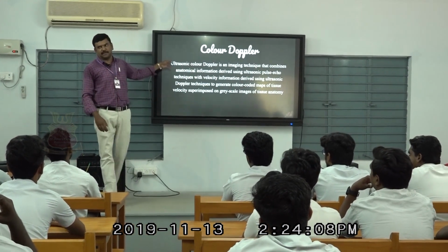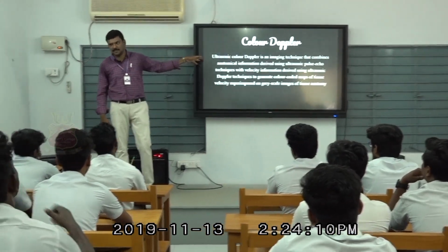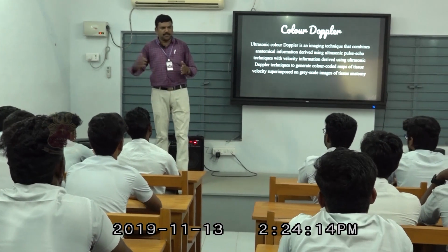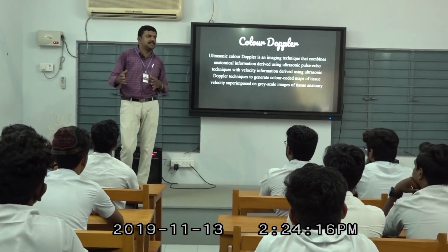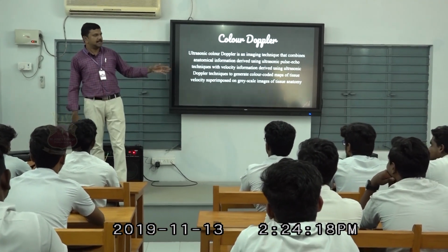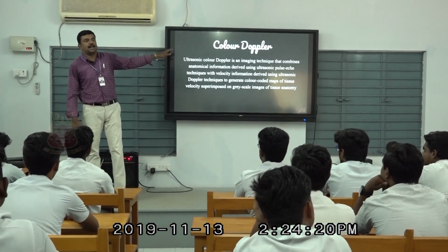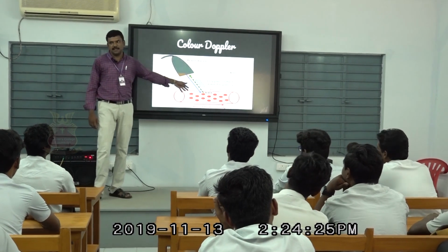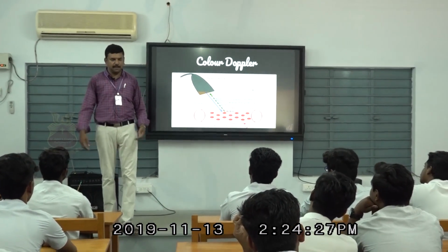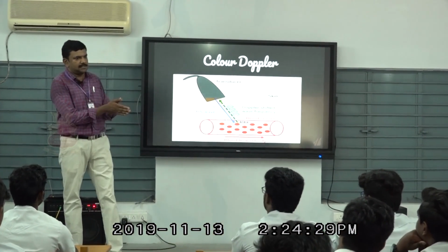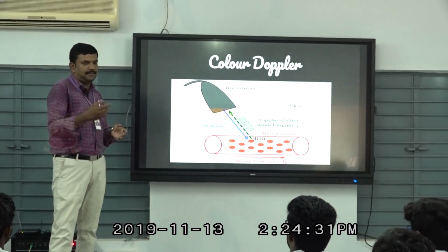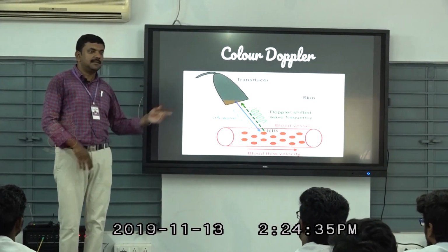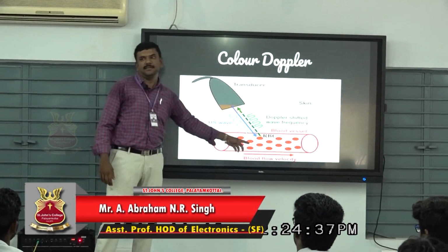That is due to the Doppler effect. Doppler is the name of a scientist. He studied the effect and it is called the Doppler effect. The approaching or departing will change the frequency of the audio. The similar way is used in this, and the ultrasound frequency is altered by the speed of the red blood cells of our body. When there is a blood flow, if you direct an ultrasound range sensor, the return wave will have some varying frequency depending upon the velocity of the blood.